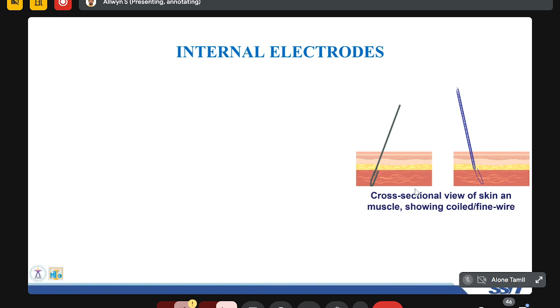Usually, it's around 0.5 to 10 micrometer here. This one. So the outer is made up of glass, inside is made up of metal. So that's why it's called a metal electrode. So in order to measure one particular cell, we use such a thing. So this solid metal is made of tungsten. It's made up of tungsten microelectrode with the glass support, used for extracellular recording, typically brain or any neurons.